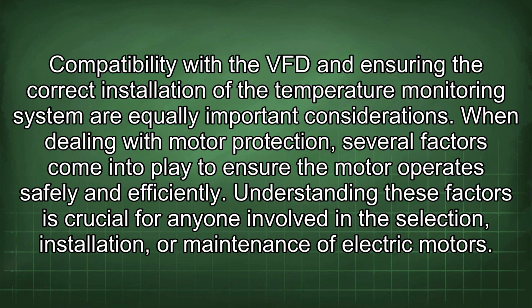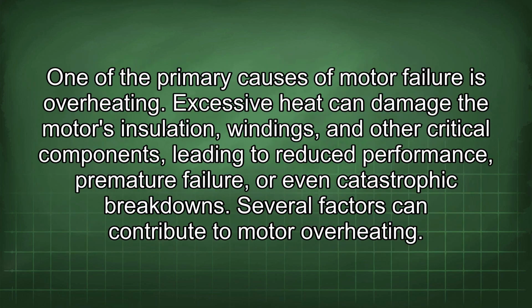When dealing with motor protection, several factors come into play to ensure the motor operates safely and efficiently. Understanding these factors is crucial for anyone involved in the selection, installation, or maintenance of electric motors. One of the primary causes of motor failure is overheating. Excessive heat can damage the motor's insulation, windings, and other critical components, leading to reduced performance, premature failure, or even catastrophic breakdowns. Several factors can contribute to motor overheating.